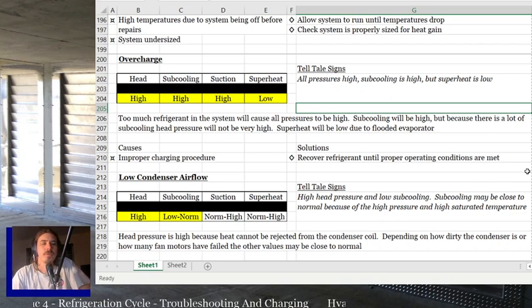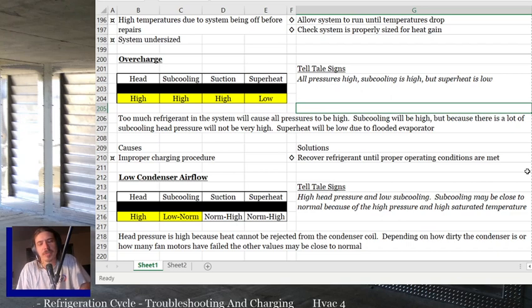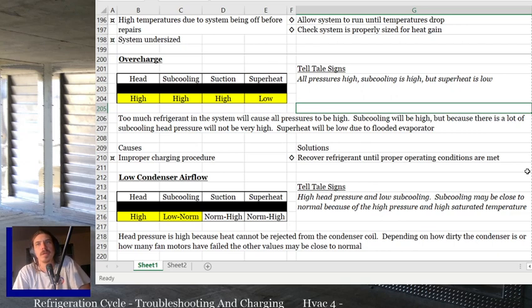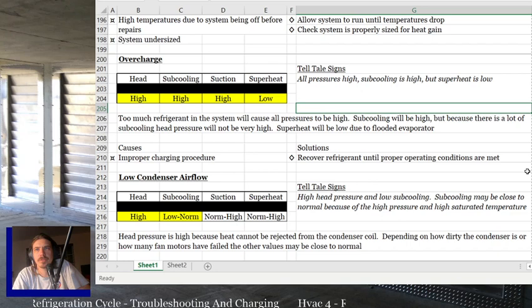So if a dirty condenser would put you at 400, and normal pressures are 200, that overcharge is going to be at 300. It's going to kind of be in between a dirty condenser and a normal operating condition. So that'll be high and your superheat's low. Basically that's your last nail in the coffin: low superheat, with everything else being high, is an overcharge.